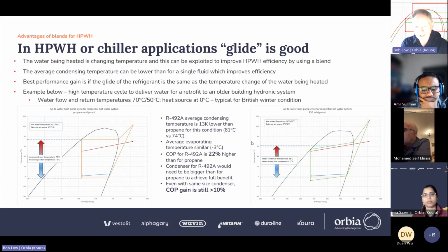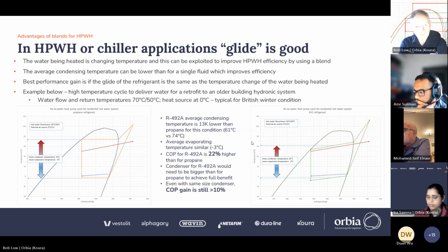The catch is the area of the heat exchanger is basically proportional to the gap between the source temperature line and the cycle temperature line. And you can just glance at the graph and see the area in the blend must be much bigger than the area in the propane cycle, because the blend has a much smaller average temperature difference.